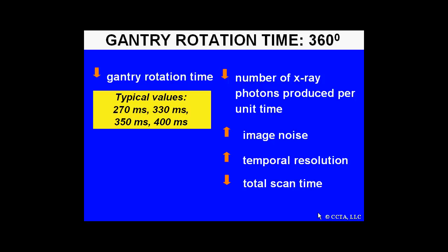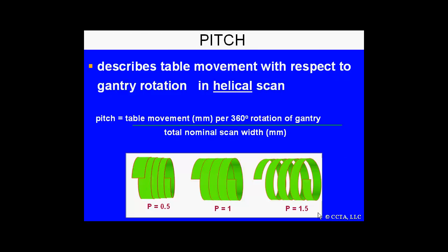The gantry rotation time can also be somewhat varied. Typical values range from 270, 330, 350, up to 400 milliseconds. Decreasing the gantry rotation time decreases the number of x-ray photons produced per unit time and increases image noise, but it also has the advantage of improving temporal resolution and decreasing total scan time.